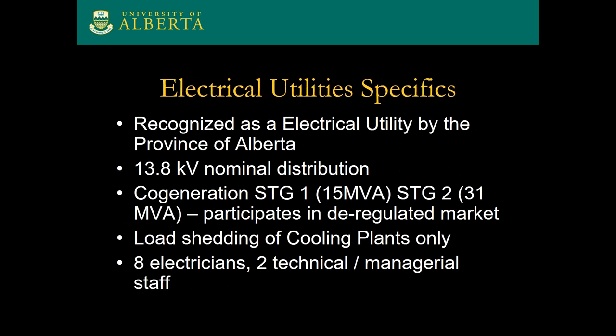Specifically for electrical utilities, we were recognized just a few years ago as a utility in the province of Alberta, and the province of Alberta is a deregulated power market, which is a little bit, I think, unique for different jurisdictions. We distribute at 13.8 kV as our nominal distribution voltage. We do have 2 cogeneration units. They're both steam turbine generators that are ultimately fired by natural gas-fired boilers. One's about 15 MVA, the other one's about 31 MVA. And we do participate in the deregulated market here in Alberta in terms of bidding in those assets.